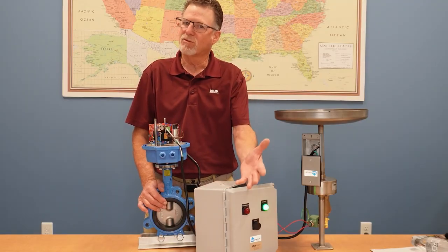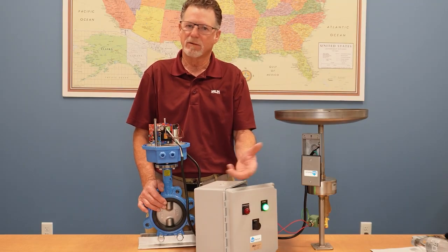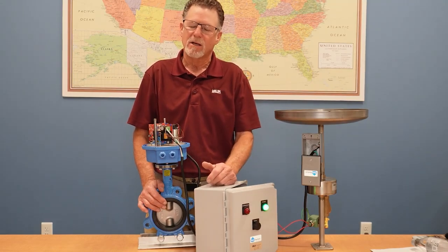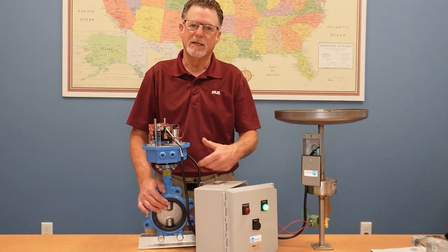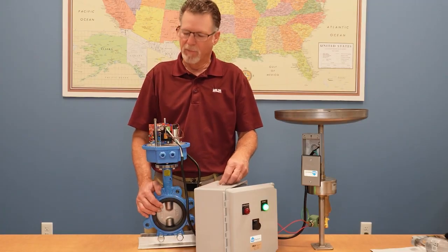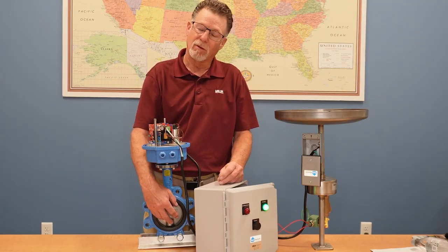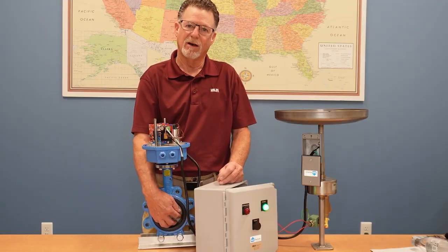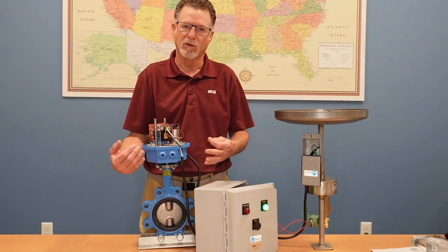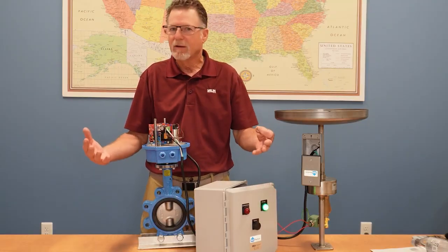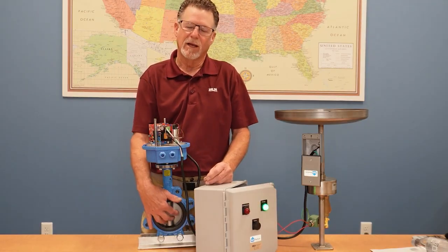The clarifier upstream should be catching any solids, rags, and any of that. So you really shouldn't be seeing it coming down into the valve. But it has happened where something has jammed in the valve and it was stuck in mid-stroke, so no lights on, can't figure out why, and they'll have an obstruction.